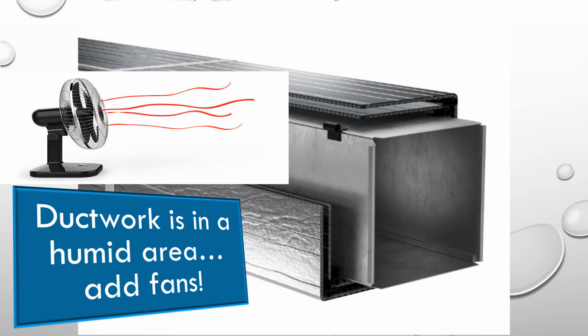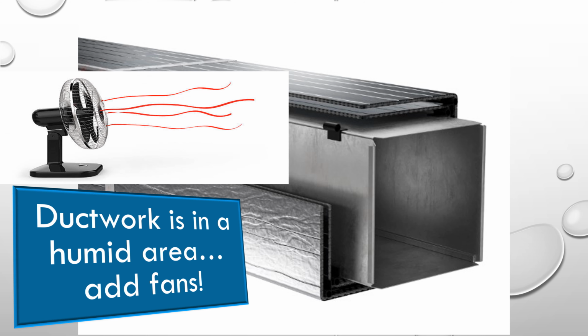The first thing we tried after this was adding a fan to the area. We thought it was humid and that the area was actually hotter than it was, and we thought that we needed to cool down the ductwork. So we sat there blowing air down on our duct system, and in attics it actually made it worse. In crawl spaces it didn't really do anything. So that idea was also a fail.